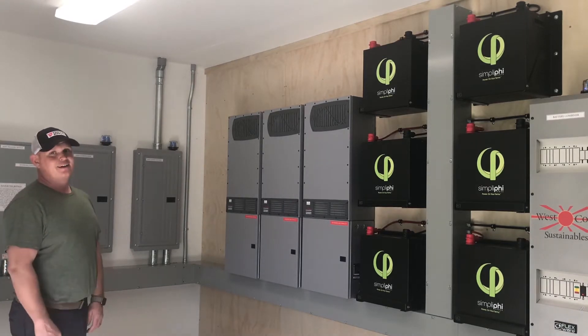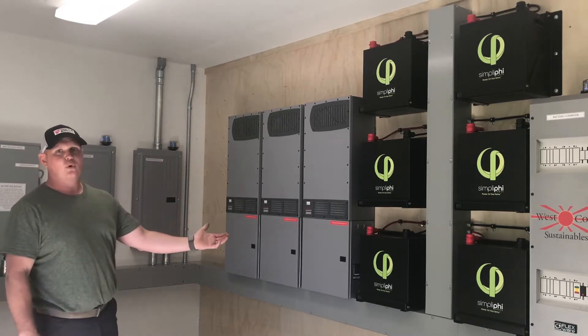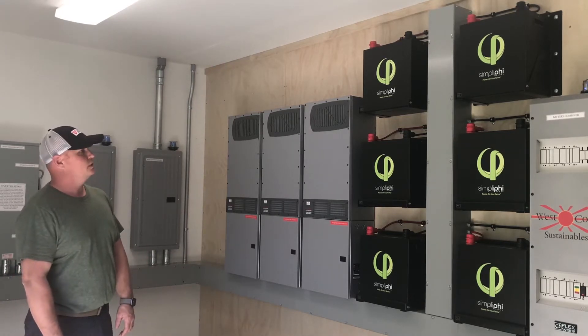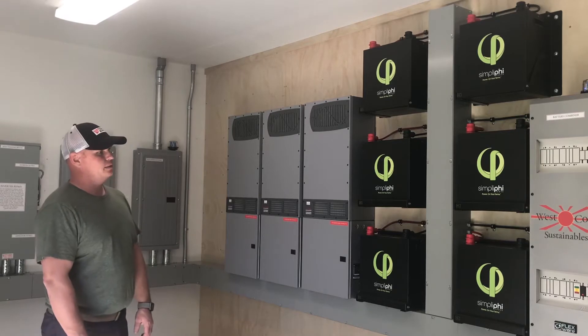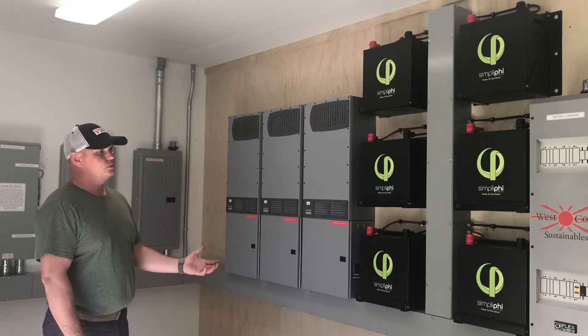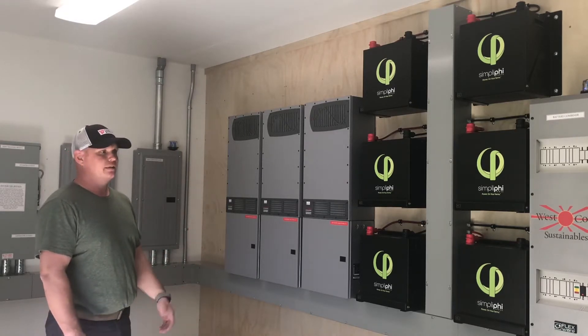It was a long one. We used some new products that we've never used before. It was our first time working with the SimpliPhi lithium battery — this is the Phi 3.4. We have 10 of them for 34 kilowatt hours of total storage. I've really had a great time working with them. We learned a lot about the wire management and the proper way to combine everything, and so far we've been super impressed with how these work. These were a very easy install and their original conception was to be a simple replacement for lead acid, and they've done that.